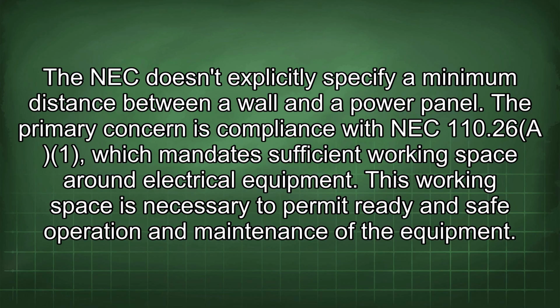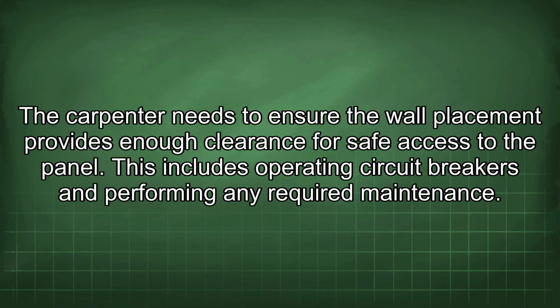The NEC doesn't explicitly specify a minimum distance between a wall and a power panel. The primary concern is compliance with NEC 110.26(A), which mandates sufficient working space around electrical equipment. This working space is necessary to permit ready and safe operation and maintenance of the equipment. The carpenter needs to ensure the wall placement provides enough clearance for safe access to the panel. This includes operating circuit breakers and performing any required maintenance.